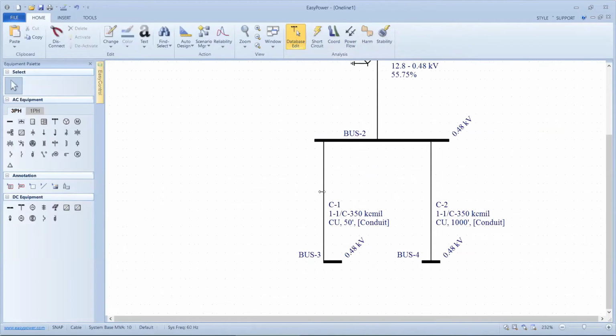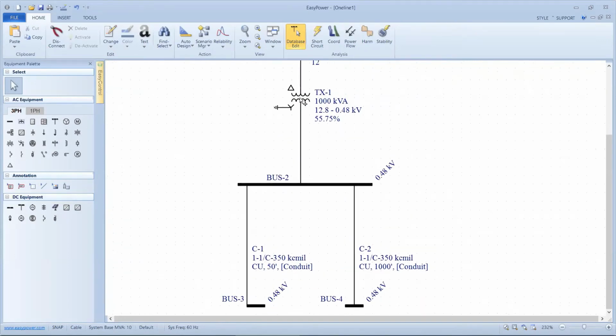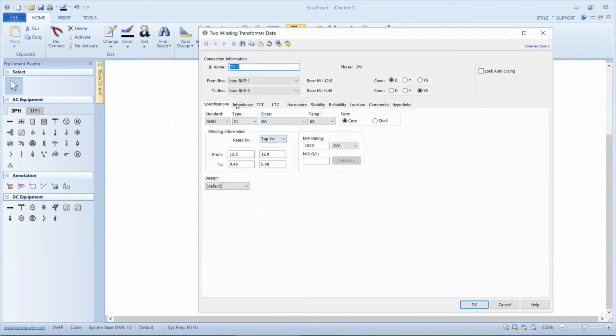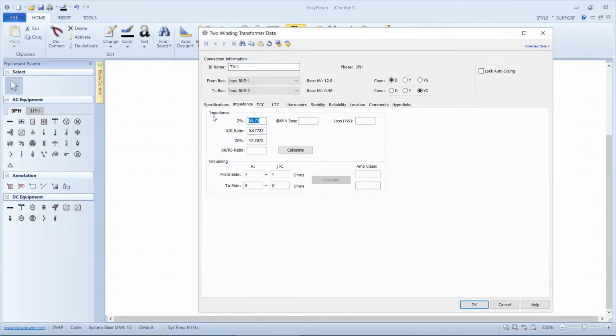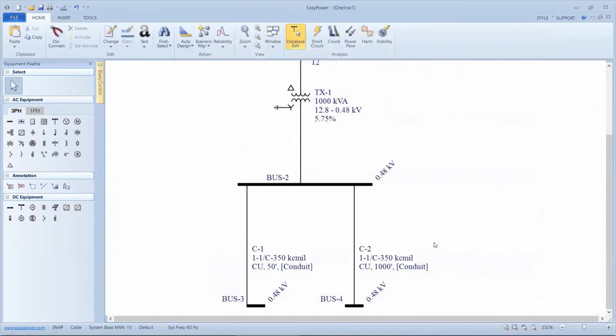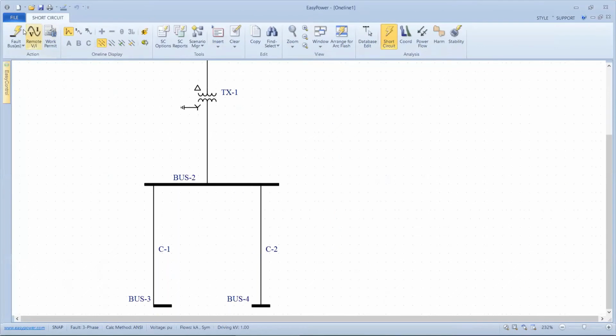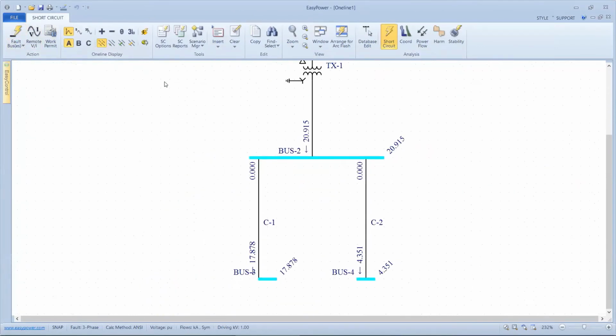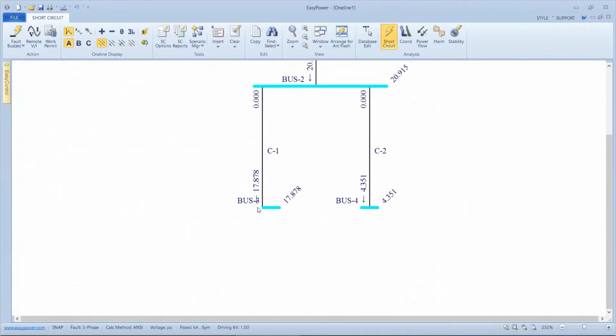Let me double check my, oh, I got too many 5s in my transformer. Okay. Go to short circuit, fault all the buses. He said this makes sense. If the transformer secondary was faulted, each phase will see 20,915 amps. If the 50-foot panel was faulted, I see 17,878 amps. And if the 1,000-foot panel had a 3-phase bolted fault, each phase will see 4,351 amps.